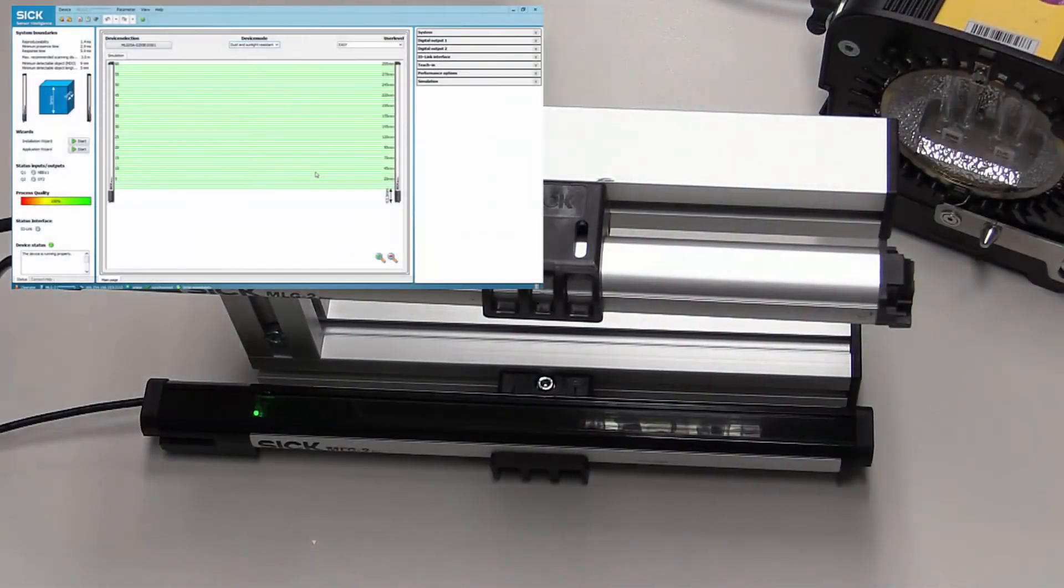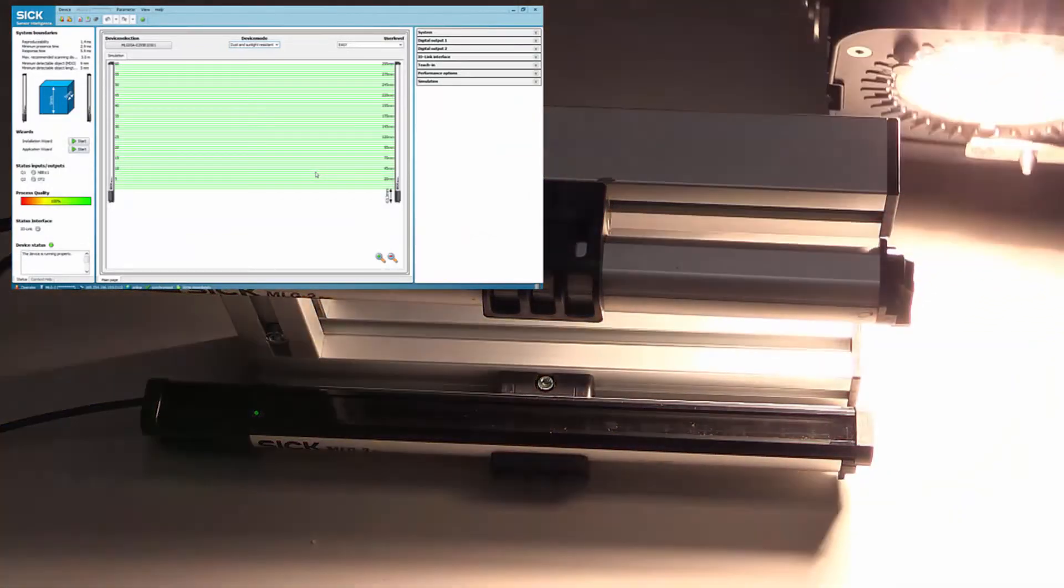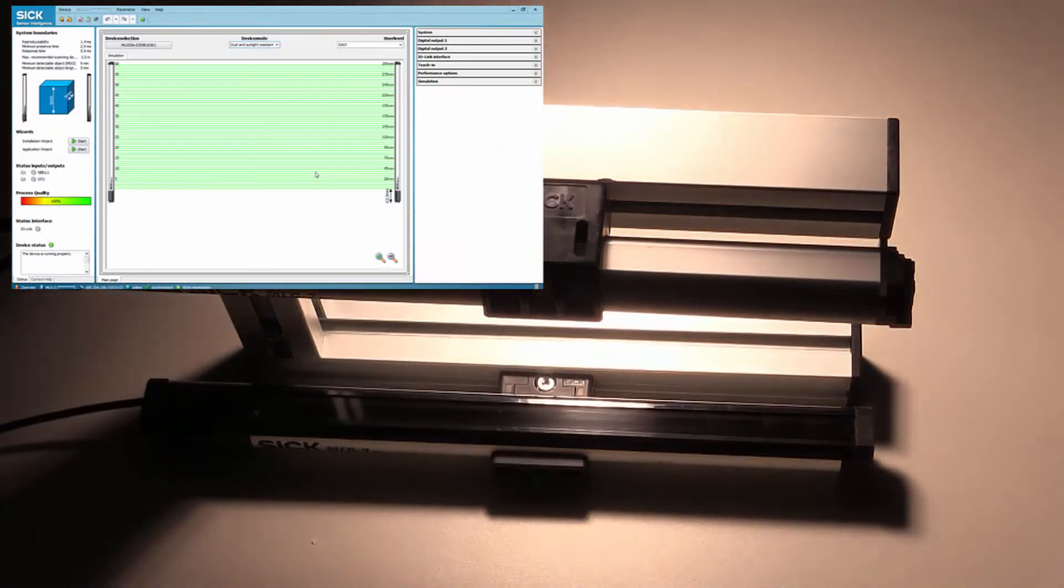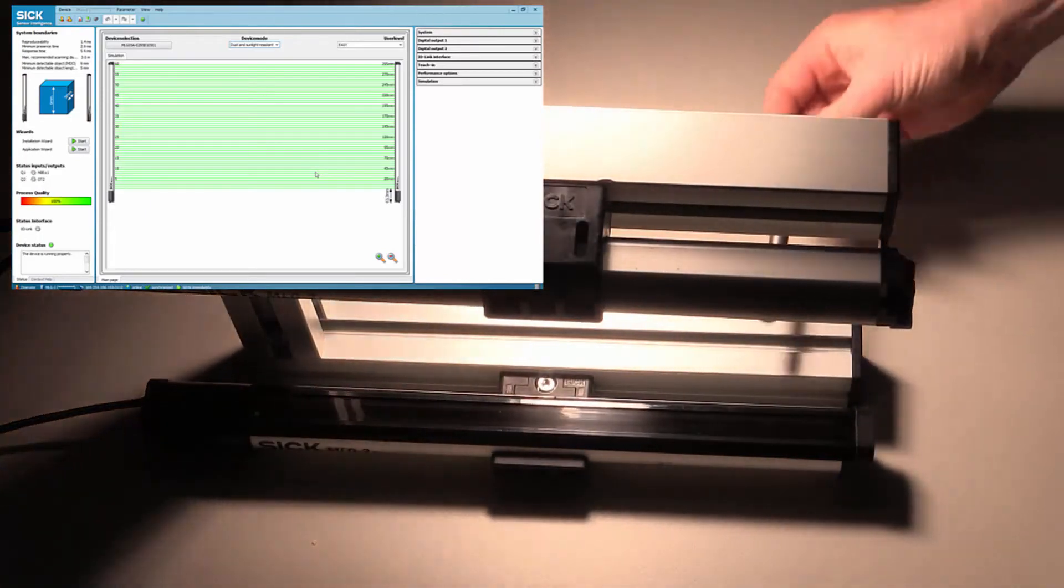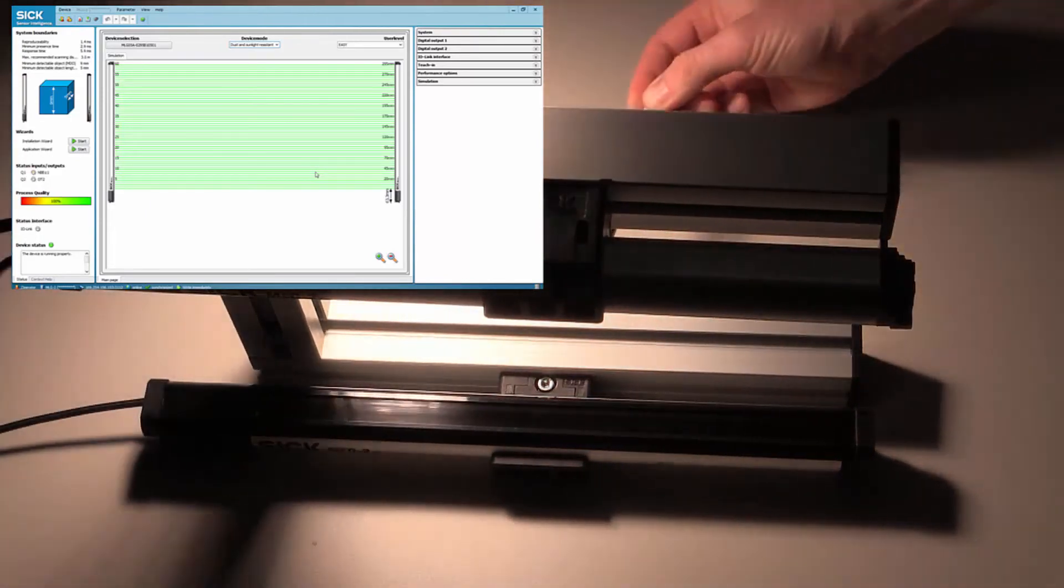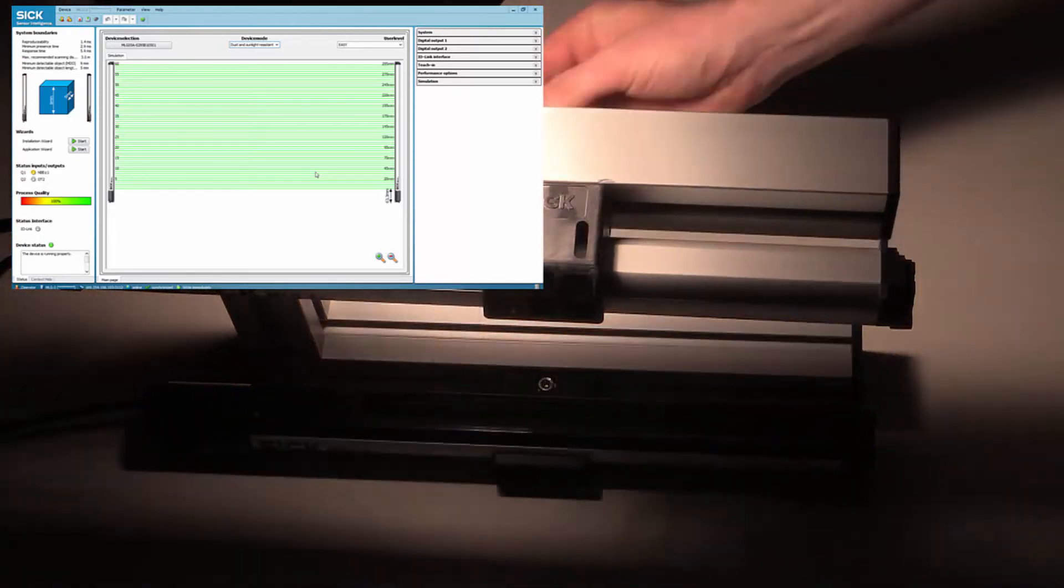The light grid is also perfect for outdoor use. Direct sunlight of up to 150,000 lux and indirect glare of 250,000 lux will not affect the detection reliability.